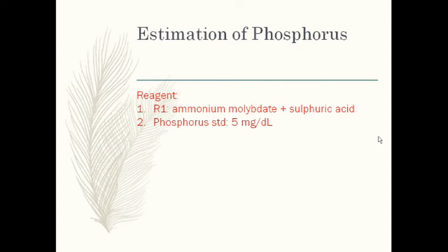Calculate the concentration by OD of test divided by OD of standard multiplied by 5. The linearity of this method is about 20 milligram per deciliter, above which you are going to dilute the sample. The serum reference range is about 2.5 to 5 mg per dl in adults. In children it's slightly higher because of the active bone growth, 4 to 6.5 milligram per deciliter, and the urine concentration is around 300 to 1000 milligrams, or 1 gram, for 24 hours.